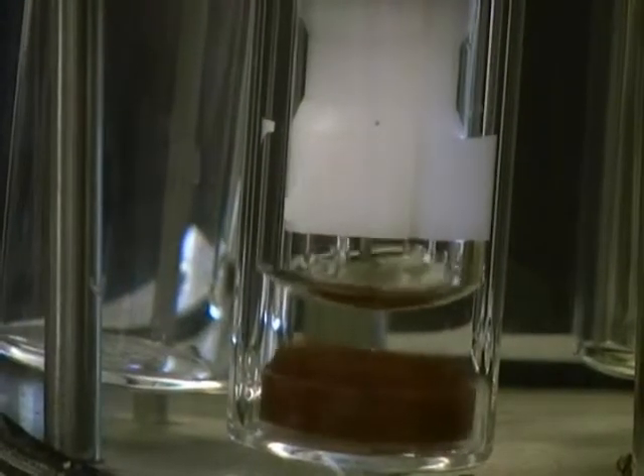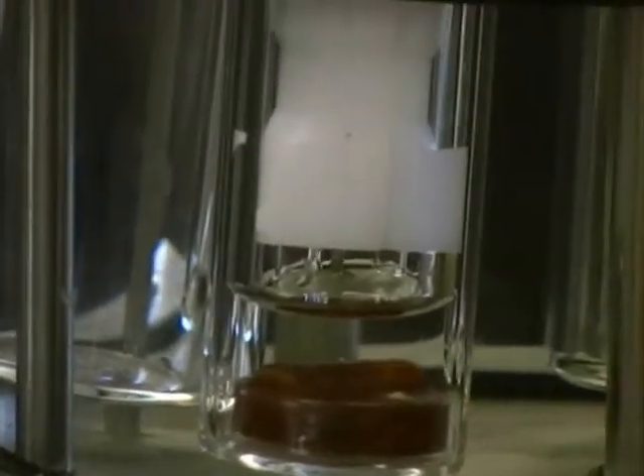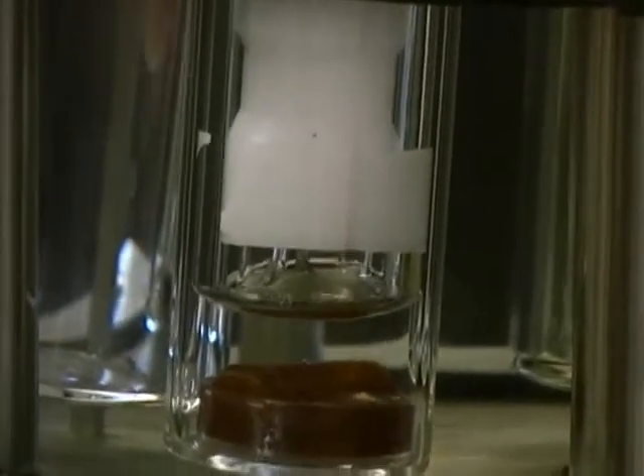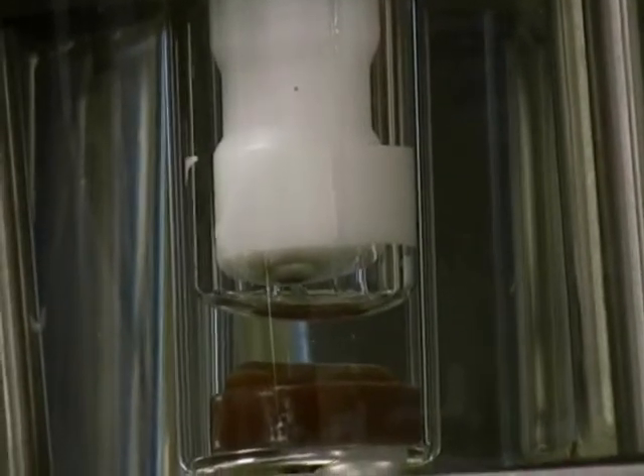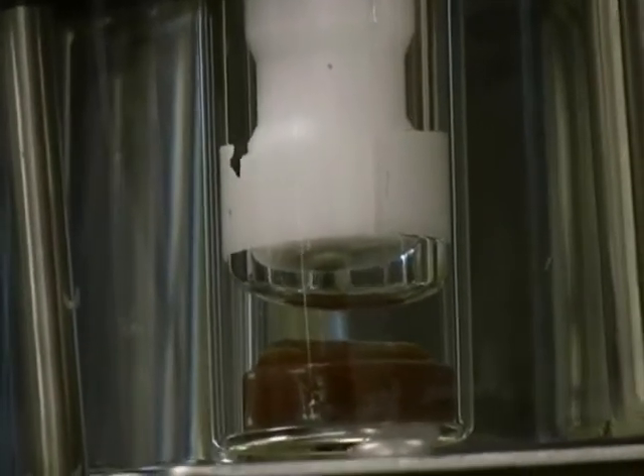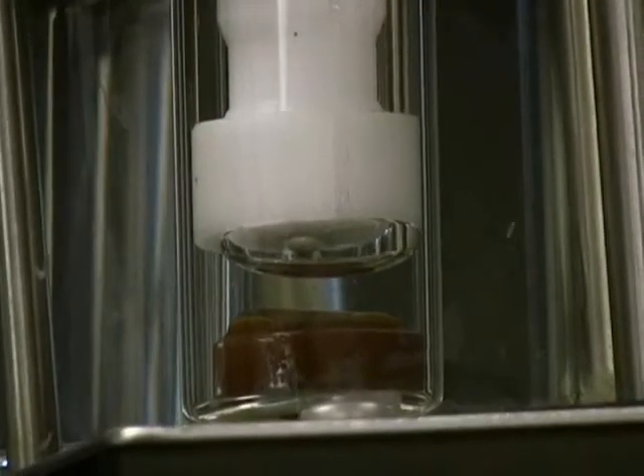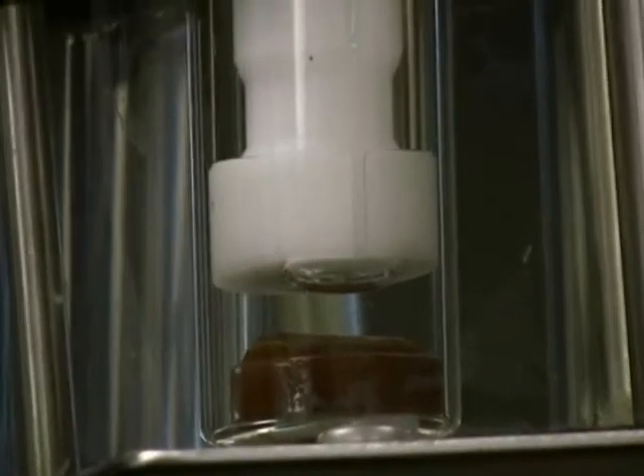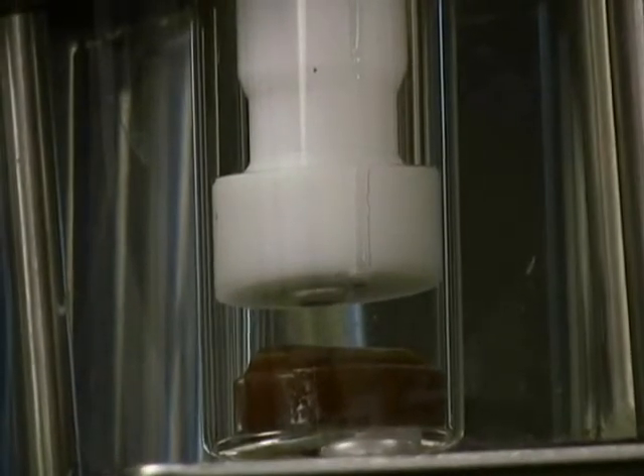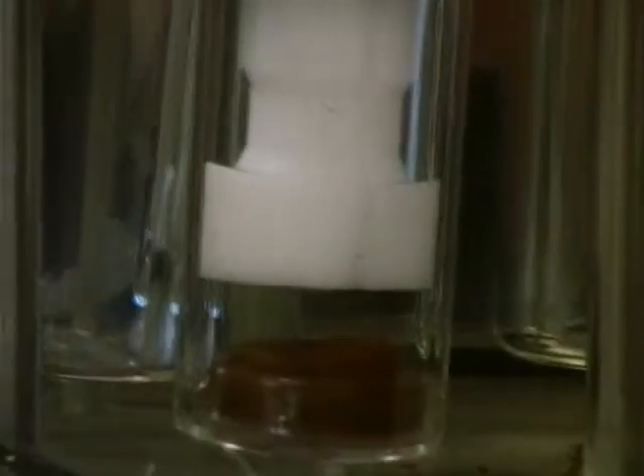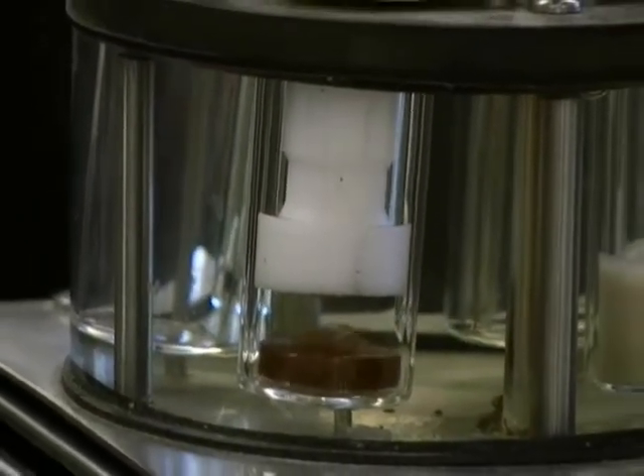using a twisting motion. When you're close to the solution you stop the stirring and then you evacuate the air from the chamber. The easy way is to lift the cell assembly and just go down slowly using the twisting motion. The air gets compressed and evacuated through the opening. The objective is to have a minimum quantity of liquid in that groove and down, and we start the stirring. So at this point we're ready to do calibration.